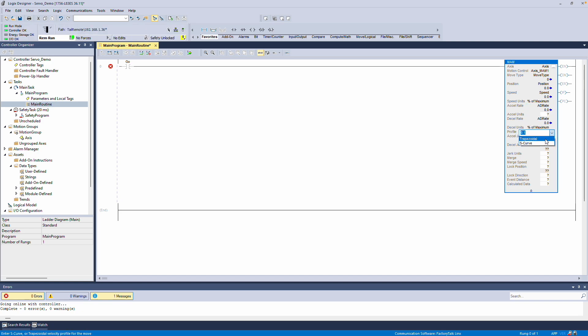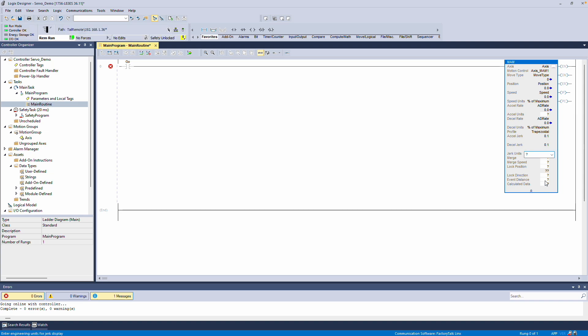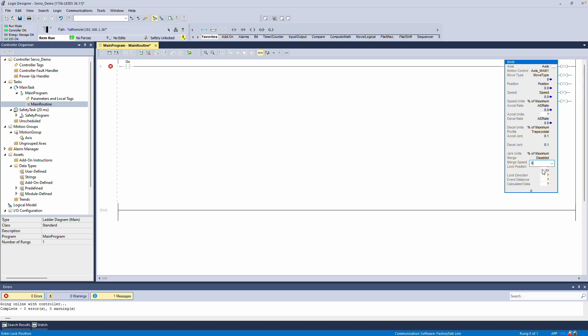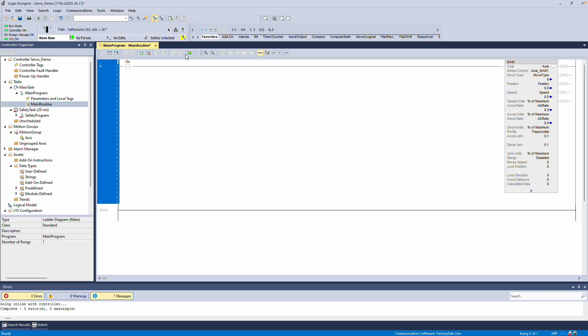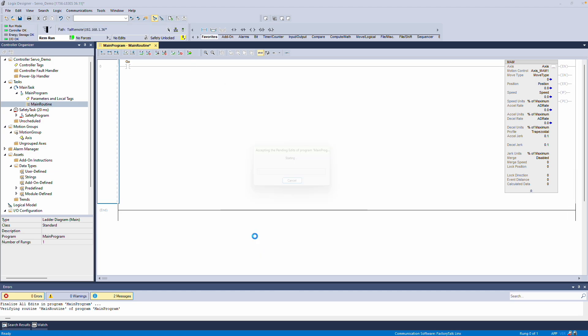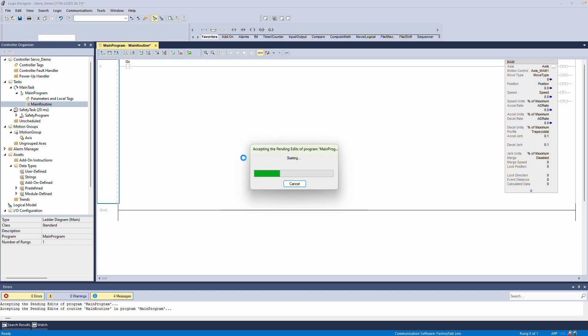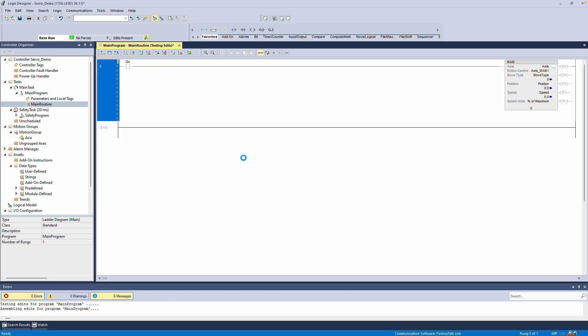For this example, I'll set the Motion Profile to Trapezoidal, and the Jerk settings will be 0.1 for both. I'll leave the Merge option set to Disabled, and all other remaining values at 0. In a real application, all of these settings should be configured according to your specific requirements. Everything is set. I'll finalize the rung.